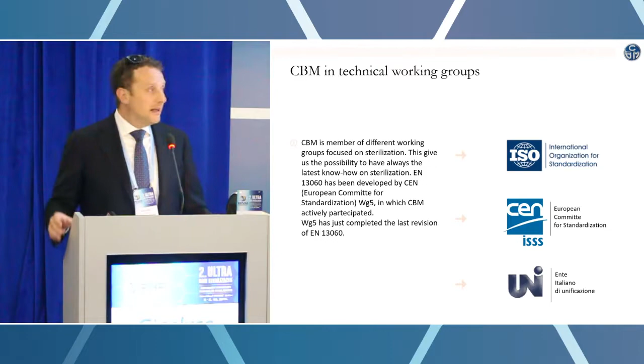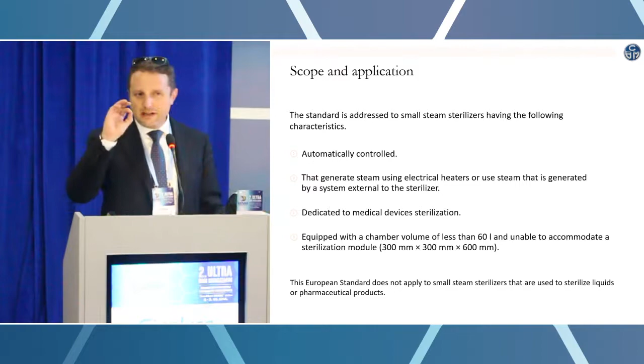And then we have two other, let's say, silly definitions. One is called narrow lumen. What is a narrow lumen? There is a specific formula, but of course you cannot take a measurement device and check all the small holes of all your devices. This is just to say that you have to look at the reprocessing instructions that should be provided by the manufacturer of each device, just to understand if your device falls inside the narrow lumen category or is a simple solid item. Just to give you an indication, a narrow lumen device is a dental handpiece, because inside the dental handpiece there are a lot of small holes that, if you take them out and put them together, would reach some meters of very, very fine internal hole.